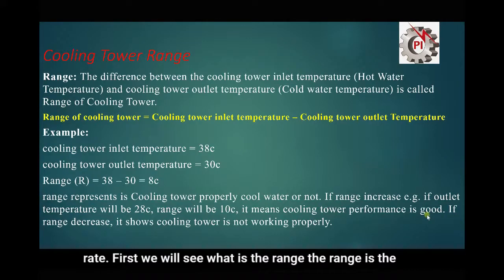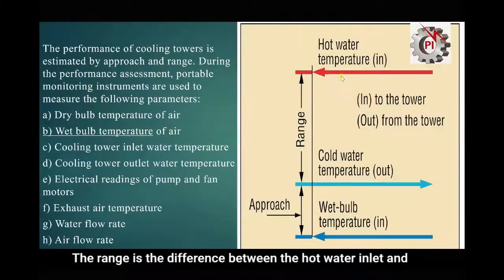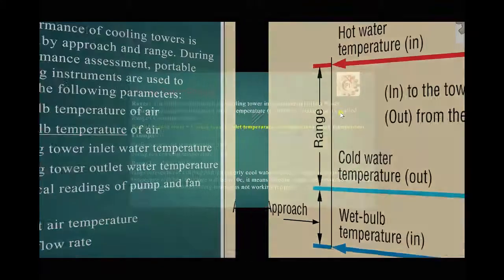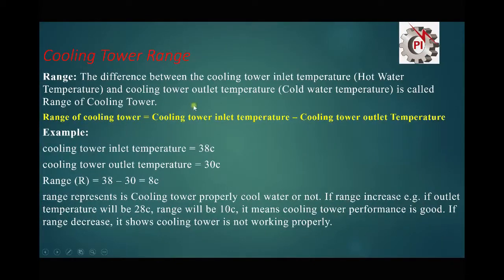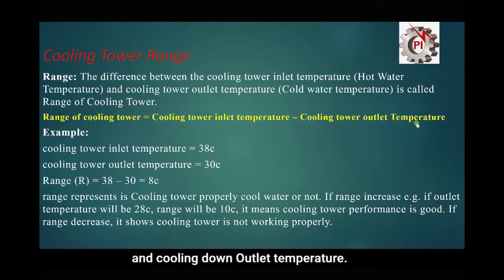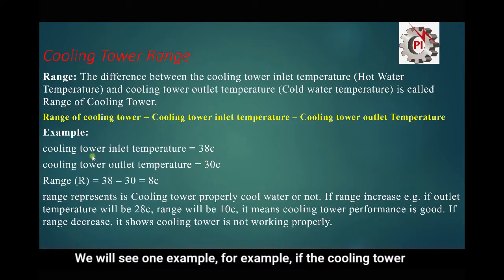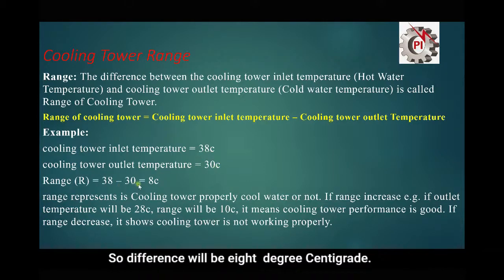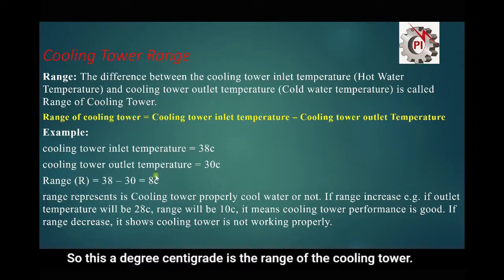First we will see what is range. The range is the difference between the hot water inlet and the cold water outlet — this difference of temperature is called the range. So the range of a cooling tower is the cooling tower inlet temperature minus the cooling tower outlet temperature. For example, if the cooling tower inlet temperature is 38°C and the outlet temperature is 30°C, the difference is 8°C, so 8°C is the range of the cooling tower.